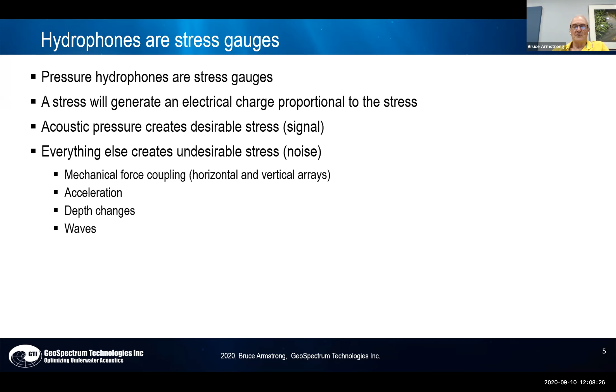So if you're building arrays, you're going to get horizontal mechanical force coupling. If you're accelerating your hydrophone, it makes noise. If you're going up and down in the water column, it senses the pressure change. If you're near the surface and there are waves, you will feel the effect of the waves. So anything that creates a force creates an output.